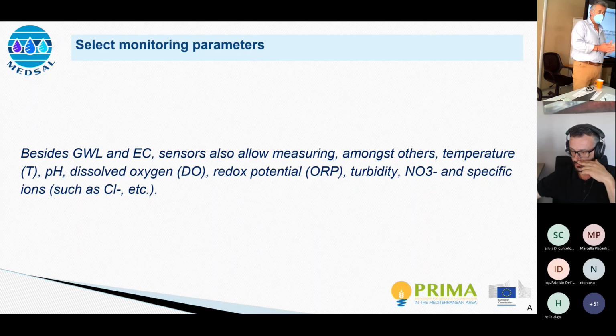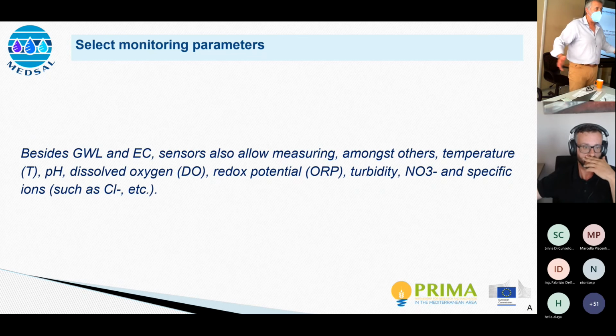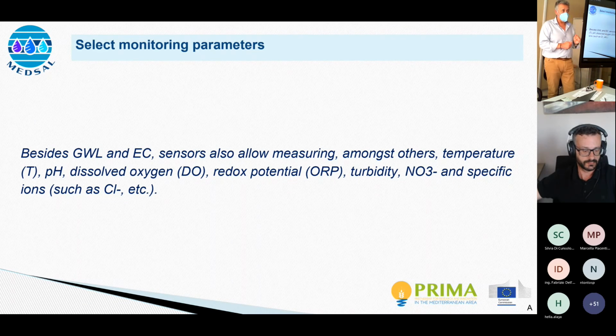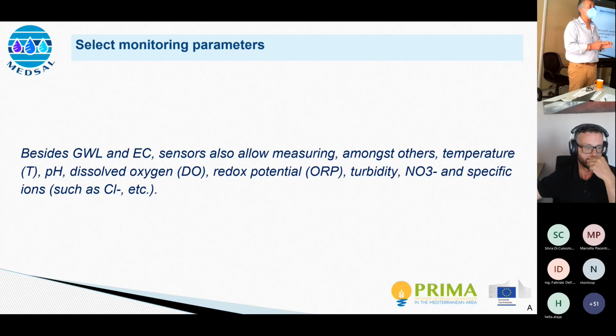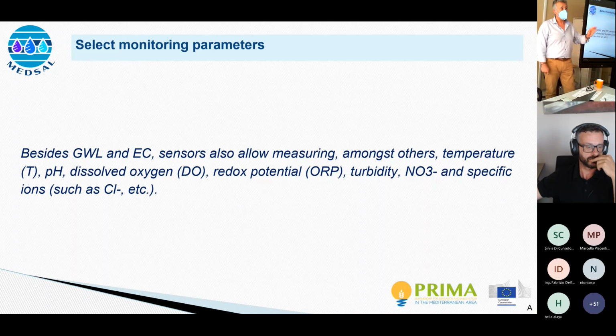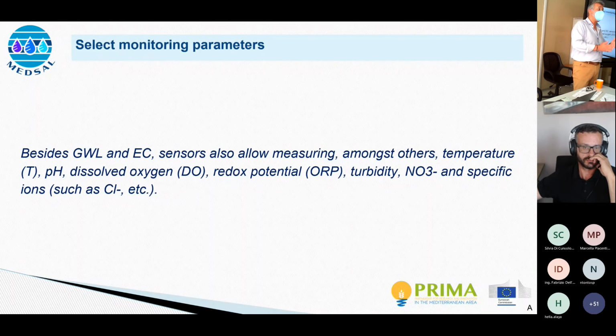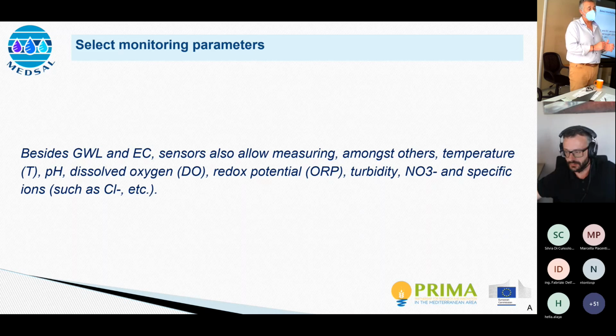Do you need everything? Not necessarily. Every time you need to decide which one you need. Just saying that I go to the supermarket and buy everything and install it is not a solution, because each parameter costs a specific amount of money. If it doesn't offer you something, you don't need to install it. The only exception is that if you decide to go for groundwater level or electric conductivity, in 99.9% of the cases you are going to have temperature measured by all means, simply because groundwater level and electric conductivity, as well as the other parameters, are temperature dependent. So to give you an accurate result, they also measure the temperature of the water. Whether they are going to give you this measurement or just use it for compensation is another story. But temperature is always measured.